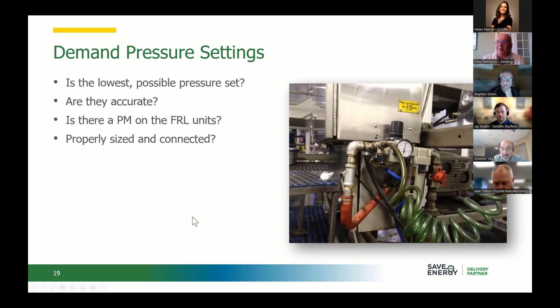I've seen one case where compressed air was used to clean the weld flash off a part. I've seen another situation where you could use a solenoid to vibrate a part clear of the work area instead of using compressed air, and that went down to about a kilowatt of power when they were originally using the equivalent of about 50 horsepower of air compressor, which at full load would be about 40 kilowatts. So it can be some pretty dramatic savings by questioning the end use.